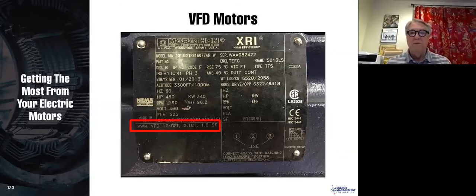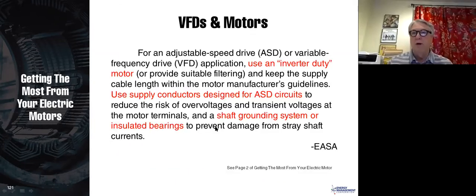Here's another nameplate. This is from Marathon, and if you look on the bottom there where I have outlined in red, it says PWM VFD, so obviously they intend for you to be able to run this motor on a variable frequency drive. And this says your 10-to-1 variable torque, but only a 2-to-1 constant torque. So here you can only run half. That's very important to know. And again, they show you it's only a 1.0 service factor when you're running on a variable frequency drive. But, and it's under the red, so you can't see it very well, across the line, the service factor is 1.15. On a PWM VFD, it is 1.0.